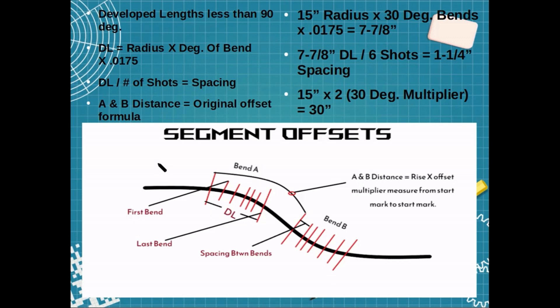Let's start off with getting the developed length of your two bends. With an offset you have two bends — Bend A and Bend B — which is typical with offsets. You need to find the developed length for these two bends.